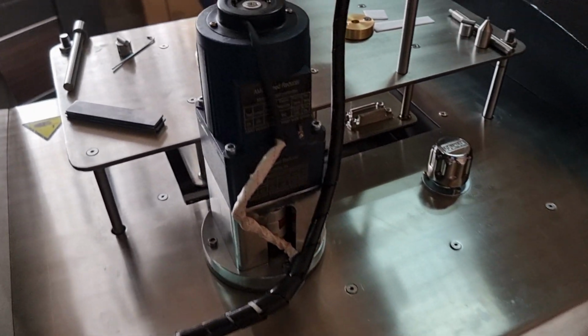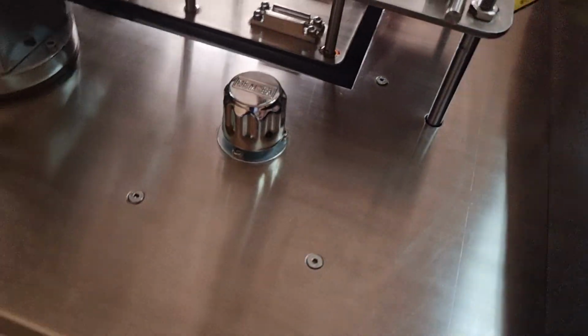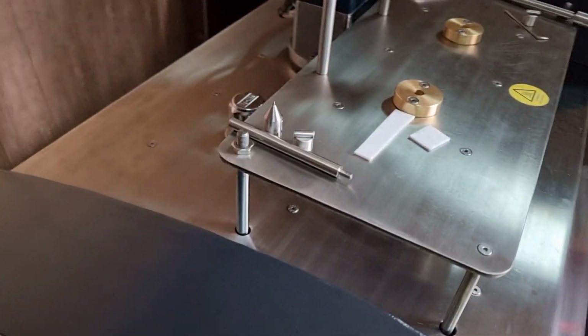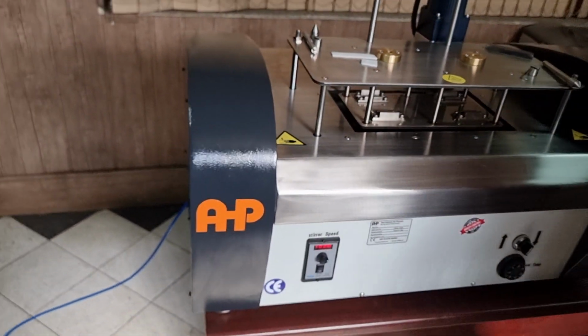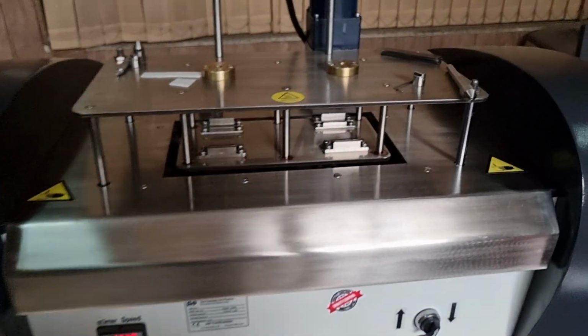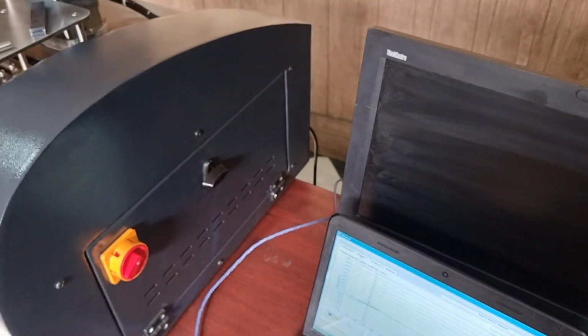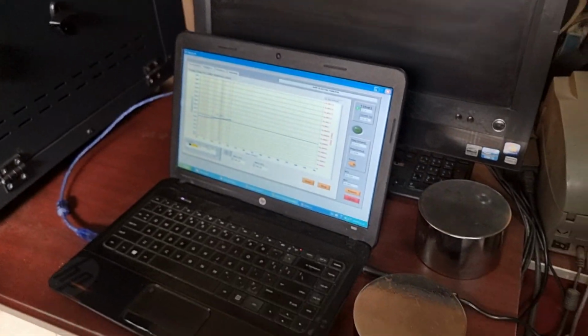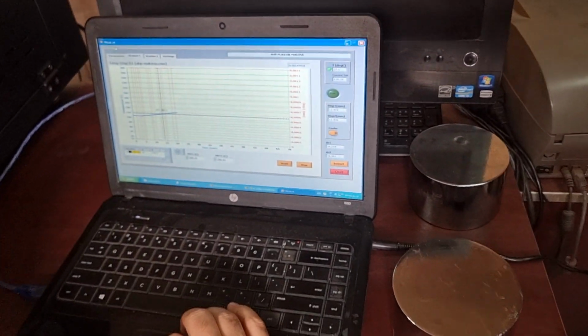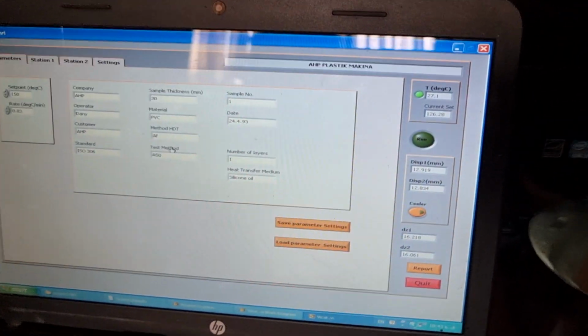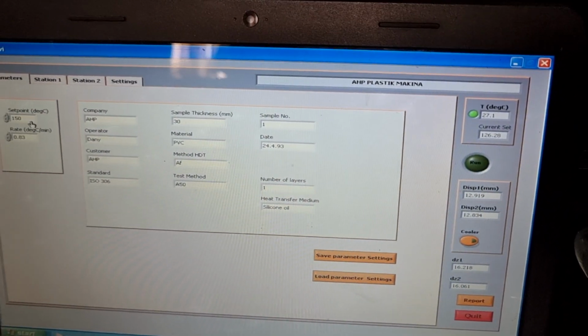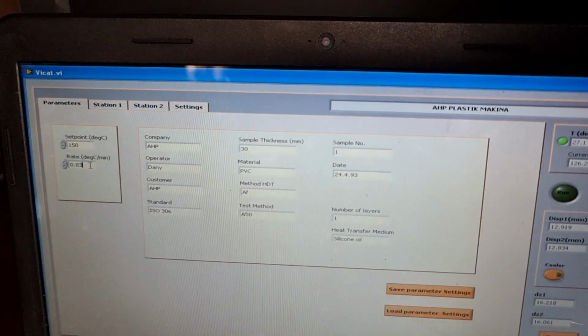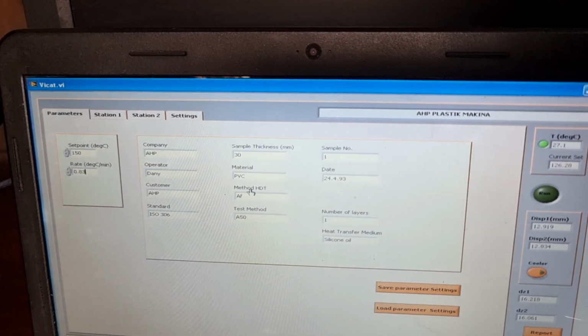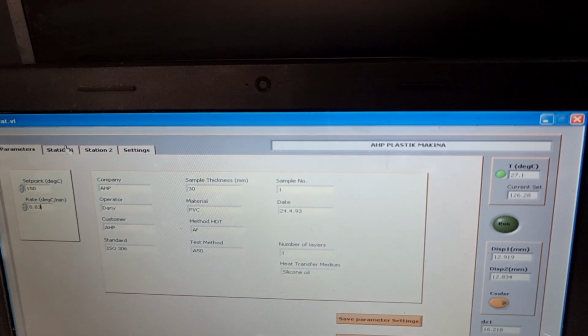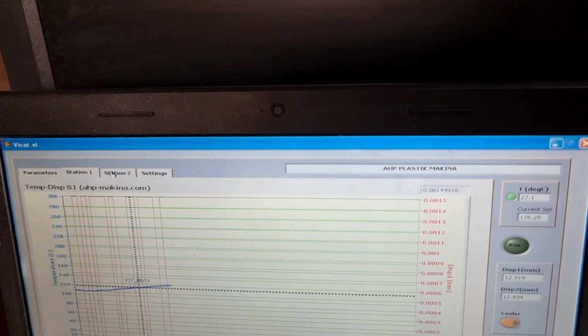Yes, and I'm going to show you how to start the test, Vicat testing. The machine has a USB connection. The control panel is on the right side, and you have a USB cable to connect the software to the machine. It's fully computerized. And the software is like this. You have parameter pages. You can set the temperature and rate of the temperature increase here, and general sample parameters will be put here. You have two stations for this specific model.